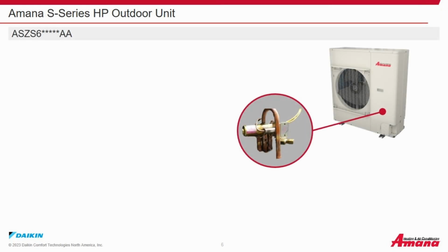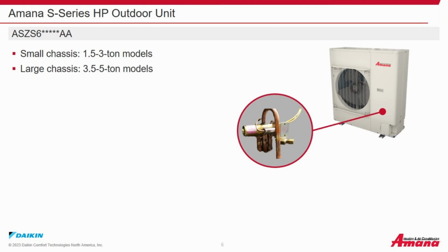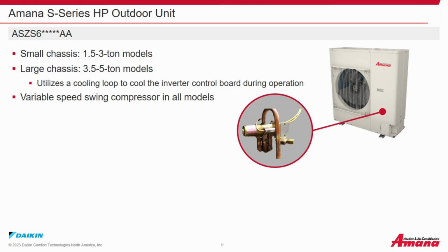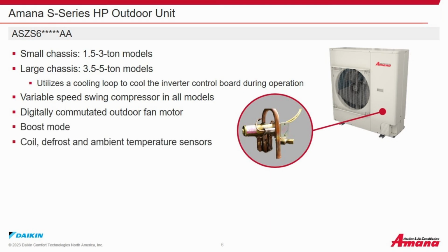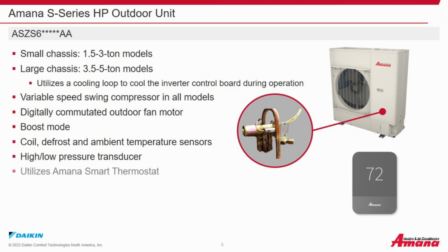The Amana S Series heat pump outdoor unit. The ASZS6AA. Small chassis, 1.5 to 3 ton models. Large chassis, 3.5 to 5 ton models. Utilizes a DX cooling loop to cool the inverter control board during operation. Variable speed swing compressor in all models. Digitally commutated outdoor fan motor. Boost mode. Coil, defrost, and ambient temperature sensors, high and low pressure transducer, and utilizes the Amana Smart Thermostat.